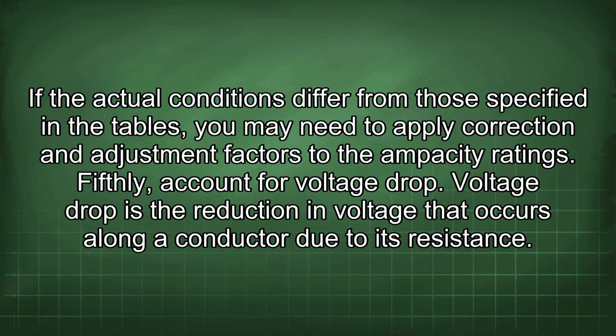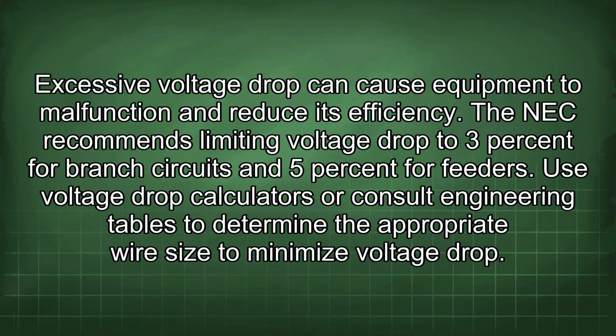Voltage drop is the reduction in voltage that occurs along the conductor due to its resistance. Excessive voltage drop can cause equipment to malfunction and reduce its efficiency. The NEC recommends limiting voltage drop to 3% for branch circuits and 5% for feeders. Use voltage drop calculators or consult engineering tables to determine the appropriate wire size to minimize voltage drop.